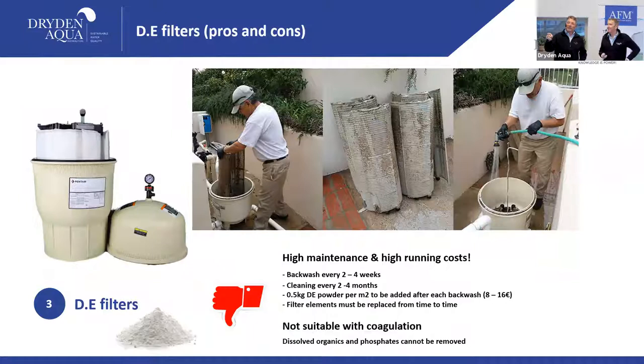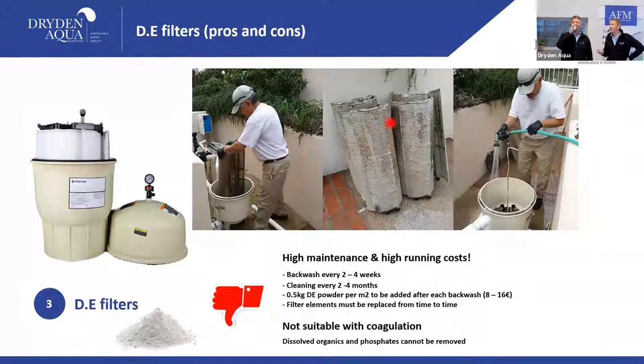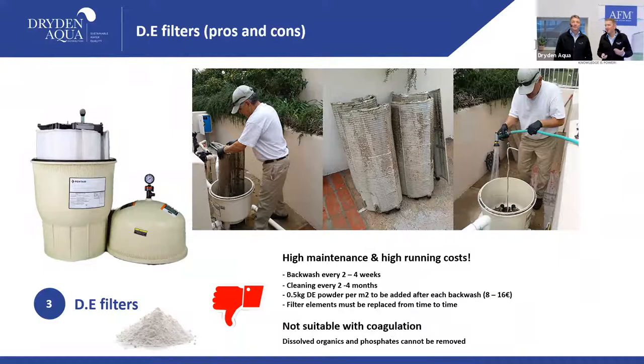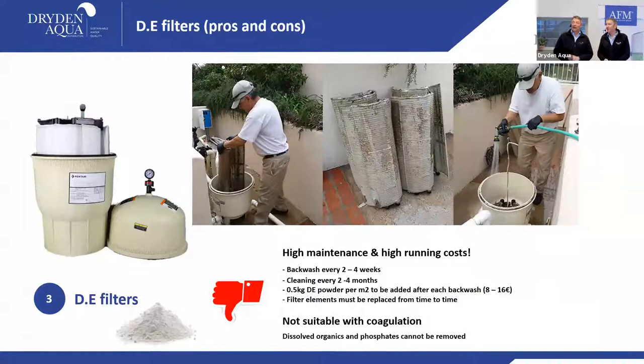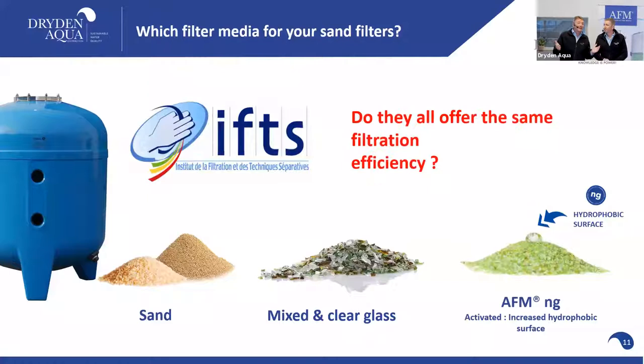Deep cleaning of DE filters is required every two to four months — you open the filter, take out the elements, wash everything down, and eventually you have to replace the elements as they break. It's high maintenance. In summary: DE is a good, bioresistant filter media with great filtration, but high maintenance, high cost, and you cannot flocculate.